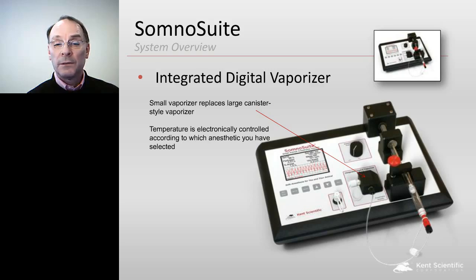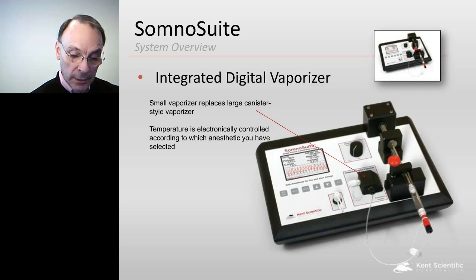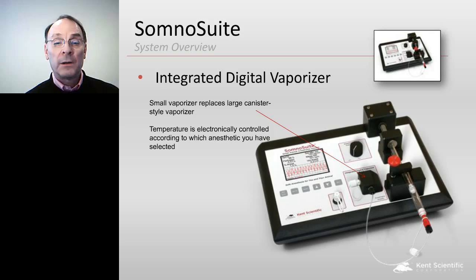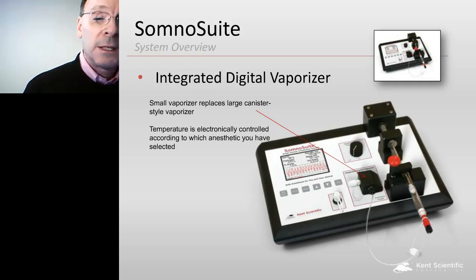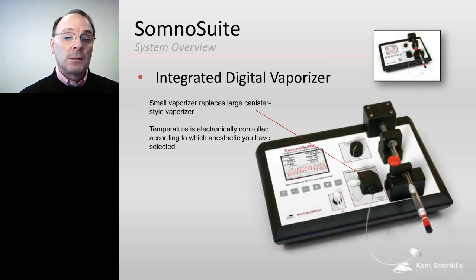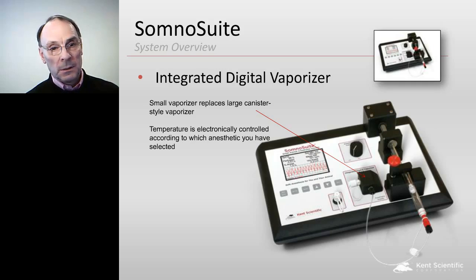the molecular weight and the vaporization temperature, the SomnoSuite does a molar calculation of the amount of air that's going out through the vaporizer block. And with that, we calculate the number of moles of the anesthetic that are needed to be delivered to the airstream to make a certain percentage. And when we test that against the test equipment, it is right on, it's dead on.